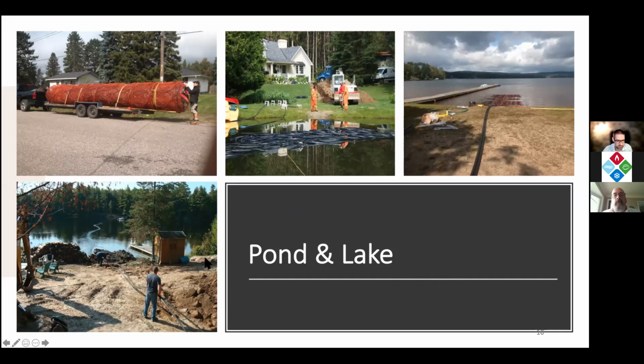Good point, because every situation is a little bit different. You've got to get out there and survey the property, see what's available or not, and make the best choice for the loops that need to go into the space. A properly sized system has to have a properly sized loop, and that can be done through different design systems - different manufacturers have different programs to help with programming and sizing your loop. But again, spacing is key in situations like this one as well.